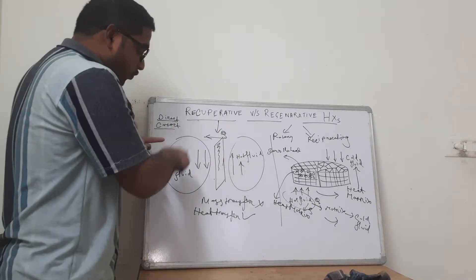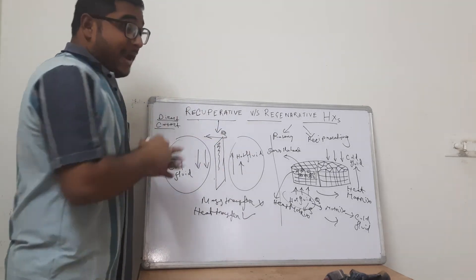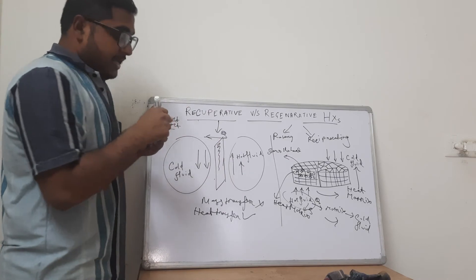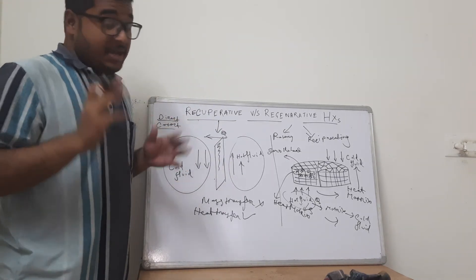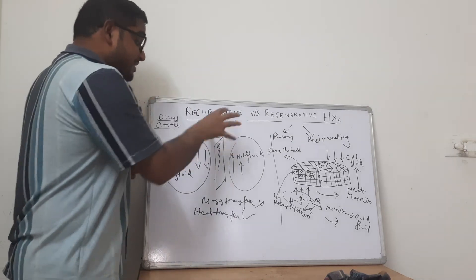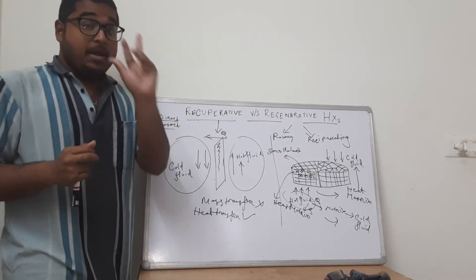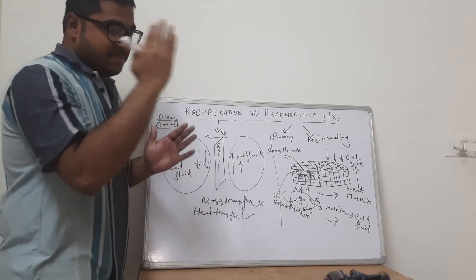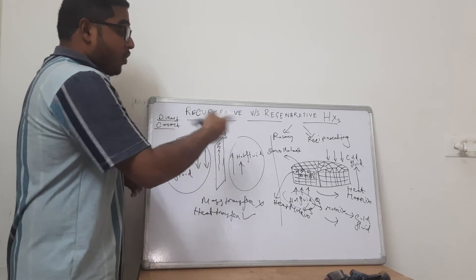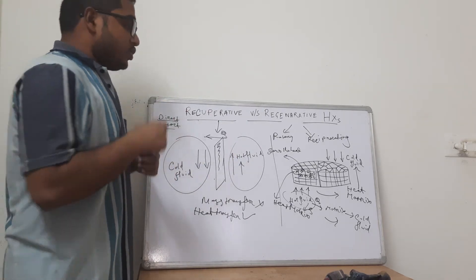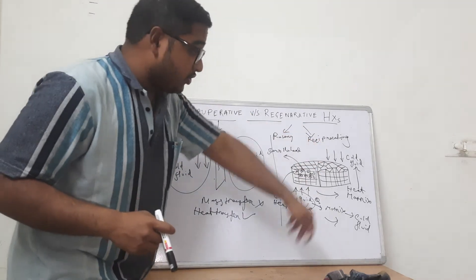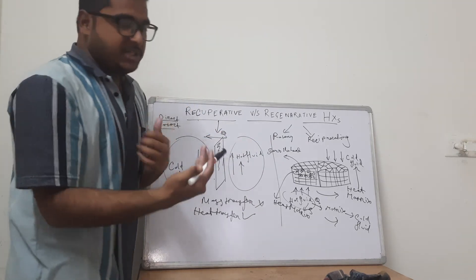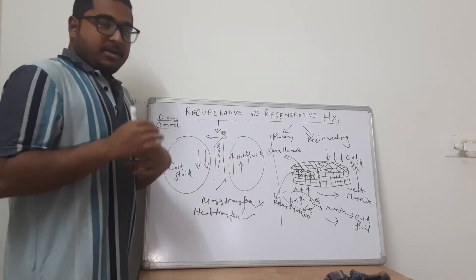In the recuperative type, the hot fluid and cold fluid move parallel or anti-parallel to each other, separated by a heat transfer surface with high conductivity that directly transfers heat from the hot fluid to the cold fluid — though it is an indirect contact method. Both recuperative and regenerative are indirect contact, but in recuperative, the hot and cold fluids are not moving through the same media; they are separated by a simple heat transfer surface where heat transfer occurs continuously. Whereas in the regenerative type, the heat absorbed from the hot fluid is transferred to the cold fluid after a certain delay, so there is always a lag in a regenerative heat exchanger.